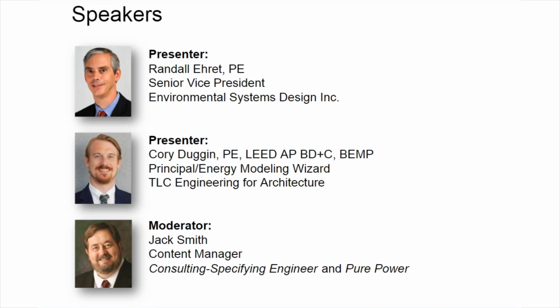What is the difference between life safety, emergency, and legally required standby systems? Thanks, Jack. For that, we've got to turn back over to Articles 700, 701, and 702 of the National Electric Code. Article 700 applies to the emergency systems, which are the life safety types of loads within your buildings. Those are required to be back on in 10 seconds or less.